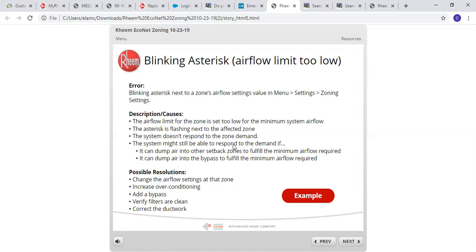The system might still be able to respond to the demand if it can dump air into other setback zones to fulfill the minimum airflow required, or it can dump air into the bypass to fulfill the minimum airflow required. Possible resolutions: change the airflow setting for that zone. Easy enough. You can increase the overconditioning. In some cases, you have to add a bypass. Big one too is verify if filters are clean. That can cause it. Or you may have to correct the ductwork.